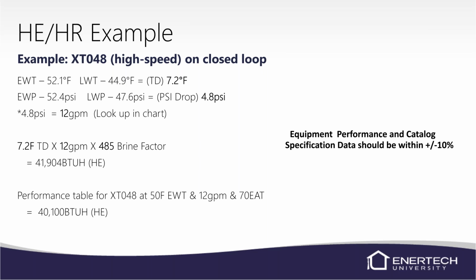If you don't have a manual, call me. I'll look it up for you. Take me 2 seconds. We'll look it up and I'll tell you yay or nay, whether it's good or bad. So if we look in the manual, XT048 at 50-degree entering water temperature and 12 GPM, it tells us that we should have 40,100 BTUs on our heat of extraction. So as long as the number that we calculated, the 41,904, is within 10% of what's in the manual, there's no need to put refrigerant gauges on the system. There's no need to really do anything else. That unit is doing all that it can.